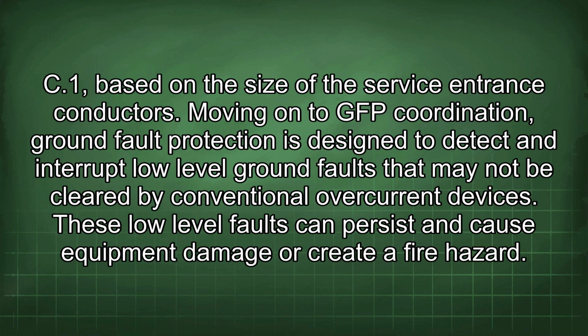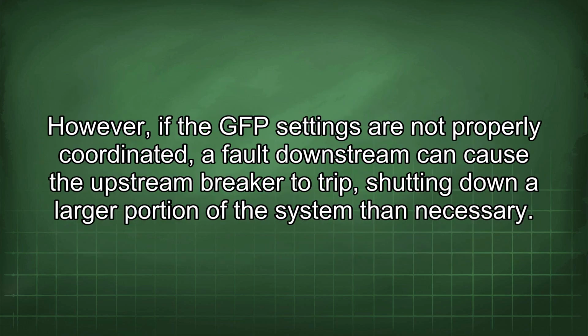Moving on to GFP coordination. Ground fault protection is designed to detect and interrupt low-level ground faults that may not be cleared by conventional overcurrent devices. These low-level faults can persist and cause equipment damage or create a fire hazard. However, if the GFP settings are not properly coordinated, a fault downstream can cause the upstream breaker to trip, shutting down a larger portion of the system than necessary.